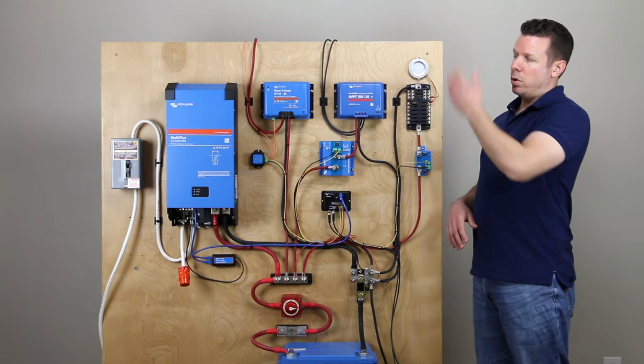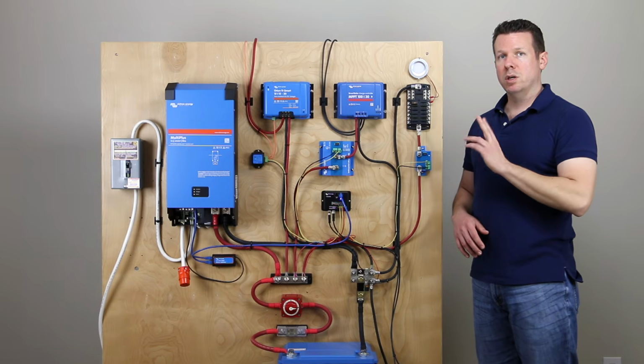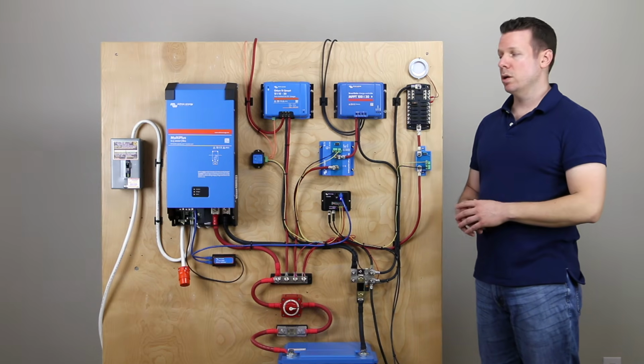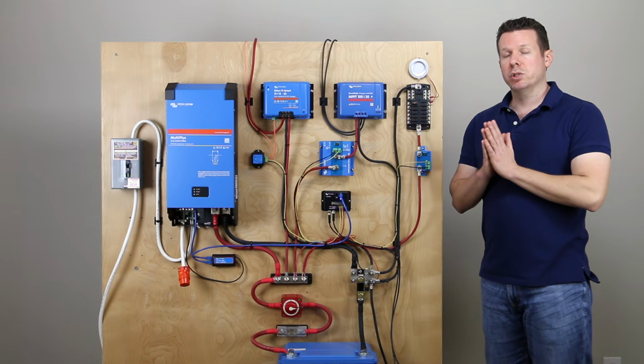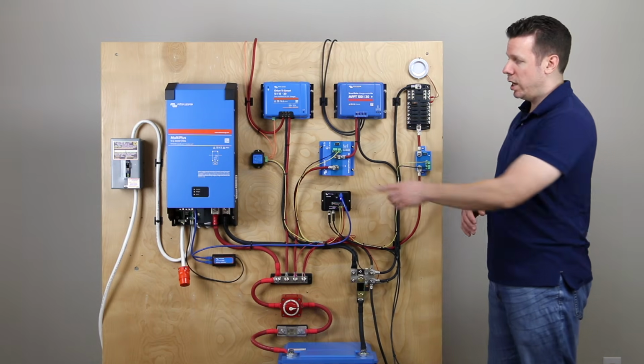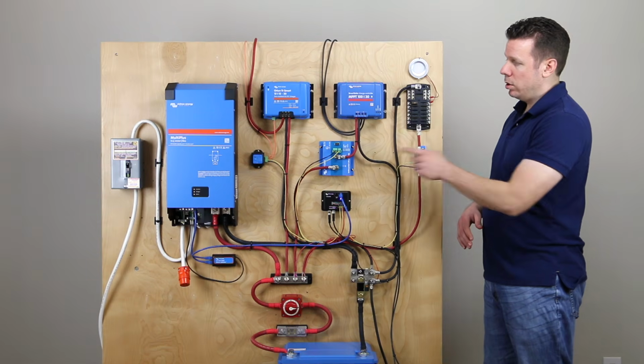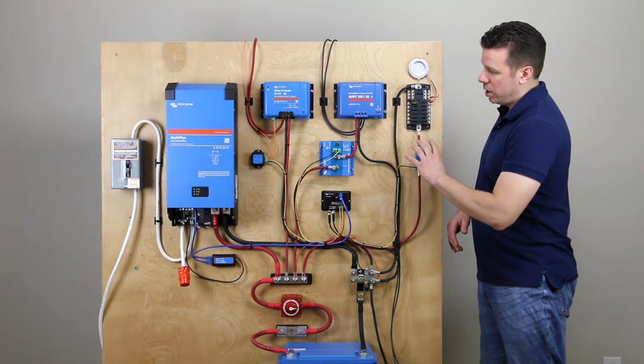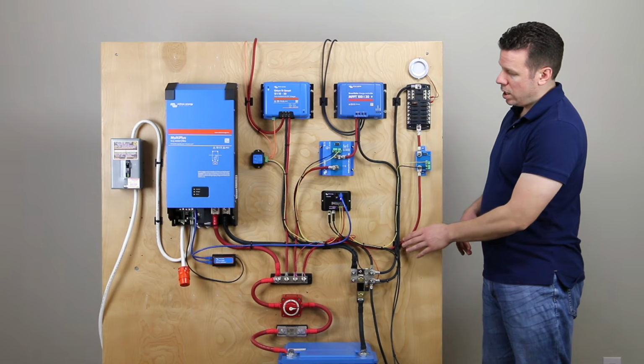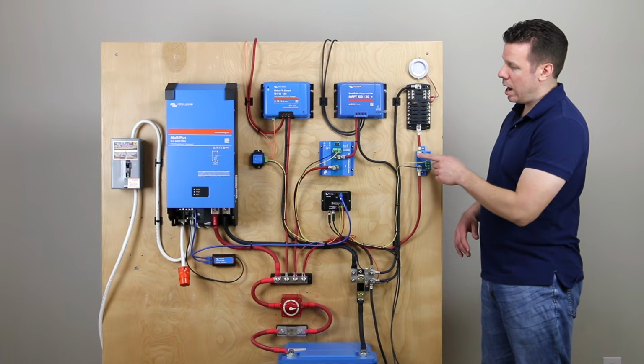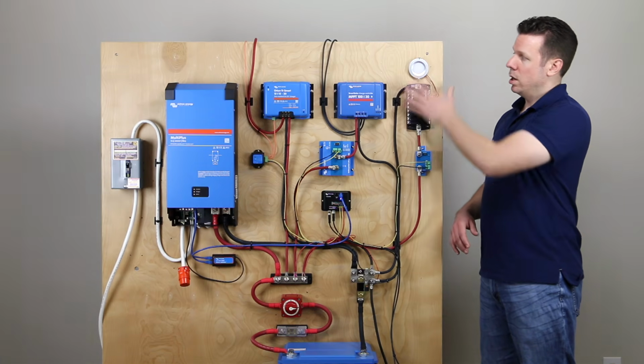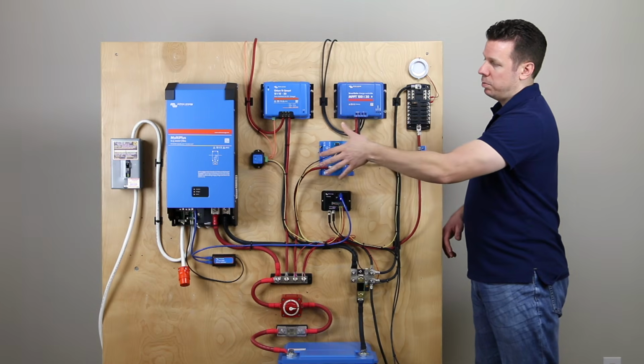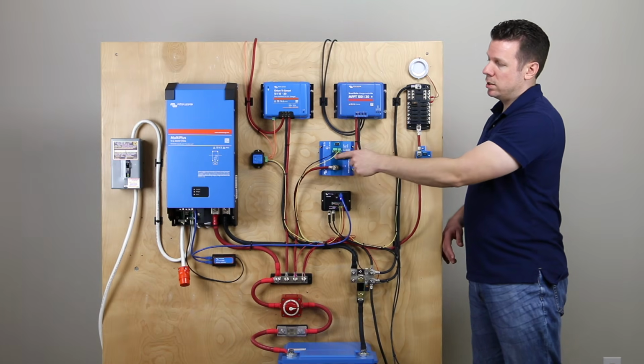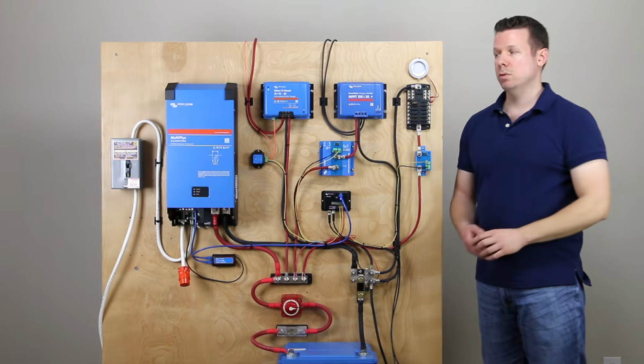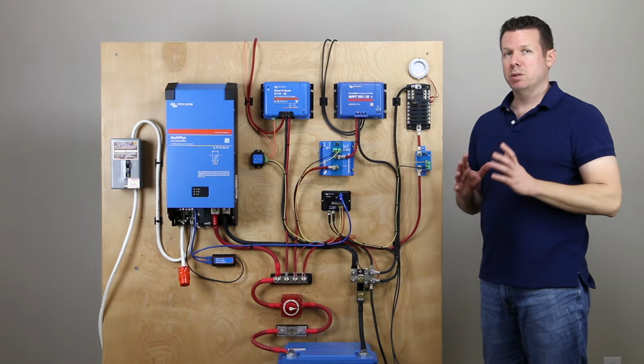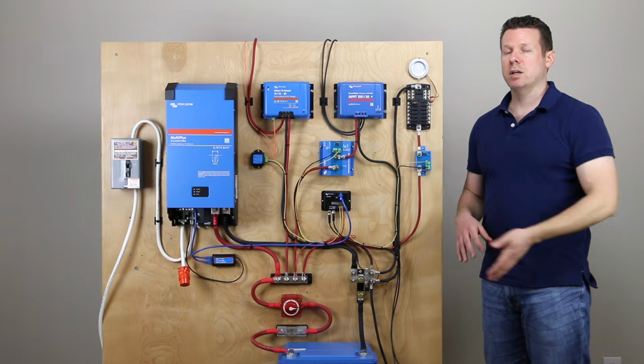As you can see, we have power going out and power going in, and you can use the BatteryProtect in both scenarios. Power is supposed to flow in one direction—look at the labels, which say in and out on the lugs, and these are flipped from each other. In this scenario, incoming power comes into this lug and outgoing power goes out to the loads. The other one is flipped around: power in comes into this side, and out goes on to the battery. That's how it works, though a small current can flow in reverse.